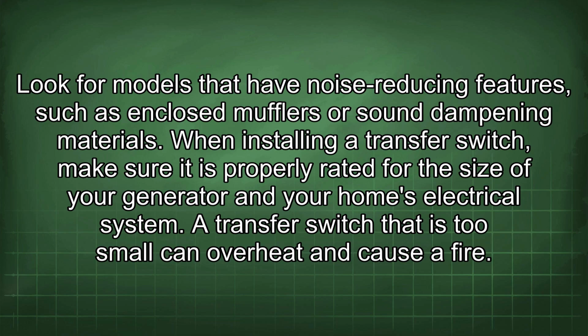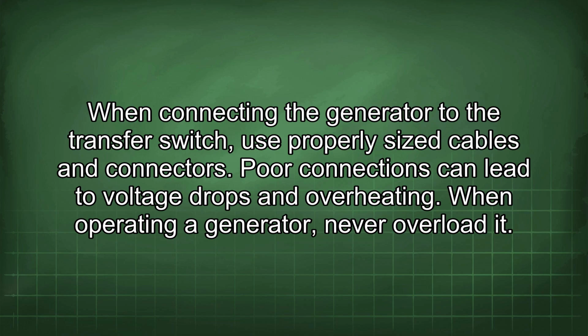When installing a transfer switch, make sure it is properly rated for the size of your generator and your home's electrical system. A transfer switch that is too small can overheat and cause a fire. When connecting the generator to the transfer switch, use properly sized cables and connectors. Poor connections can lead to voltage drops and overheating.